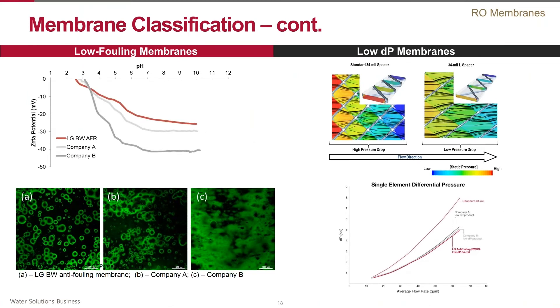Other types of membranes available on the market today are low fouling membranes and low differential pressure membranes. Low fouling membranes reduce the potential for fouling by, for example, changing the surface properties of the polyamide layer. Low differential pressure membranes can be considered a subset of low fouling membranes. These membrane modules typically have a special feed spacer with optimized geometry that leads to lower pressure drop, so feed channels will not plug as quickly with suspended solids, fouling, or scale.